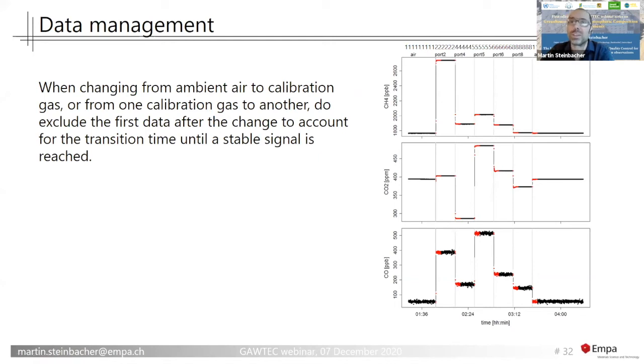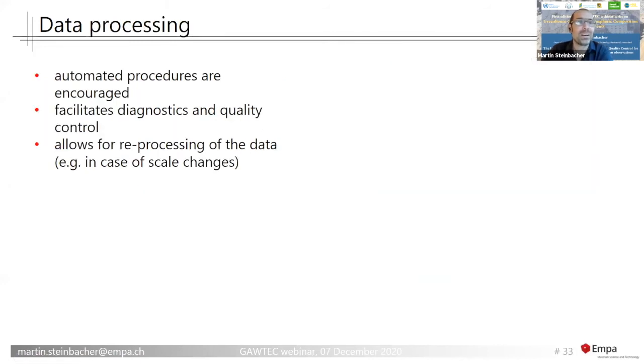And you need to record, along with the concentrations of your analyzer, the valve position, so that you know at which point in time which reference source was measured, or if ambient air was measured. And all that urgently calls for automated software and no spreadsheet solution. Well, this is what I said here. Automated processes are encouraged, facilitate diagnostics and quality control, and also allow for rather easy reprocessing of the data.